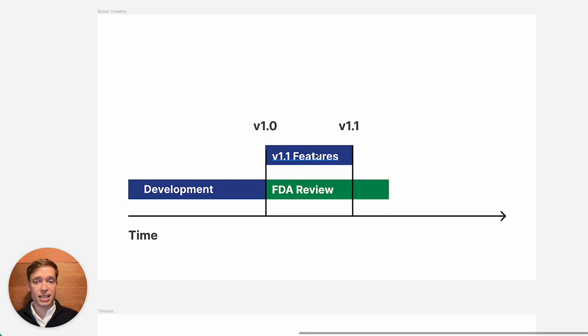And as long as, and this is critical, as long as the features in the 1.1 release are not such that they would require another 510K, then you can do what you'd call a note to file. It does involve some additional documentation for version 1.1, and often you can even complete that before the FDA review. So this not only keeps your engineering team busy, but if you have funding milestones tied to that submission, it can really help there too. Now, the main downside is you do have to do some additional paperwork, but if you're using good tooling, or if you're working with a team like ours that has great templates and a great system, this isn't so bad.